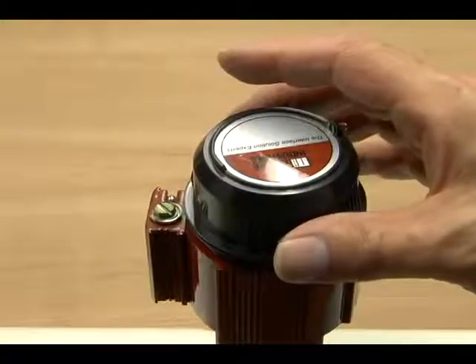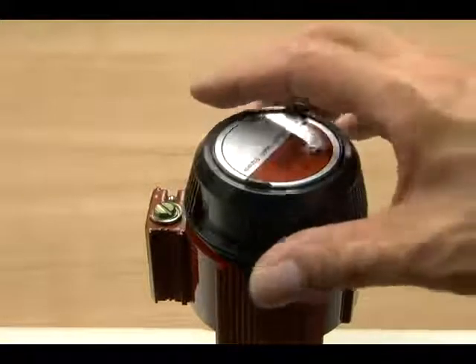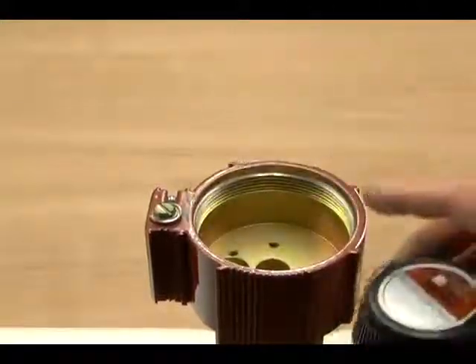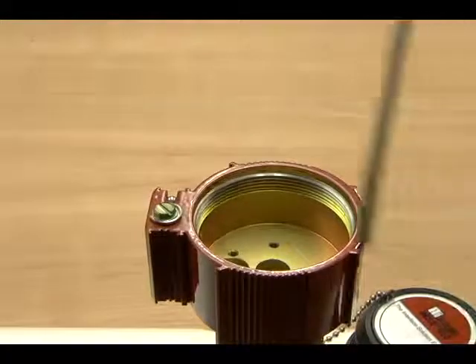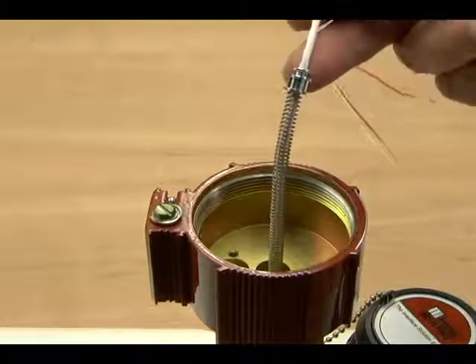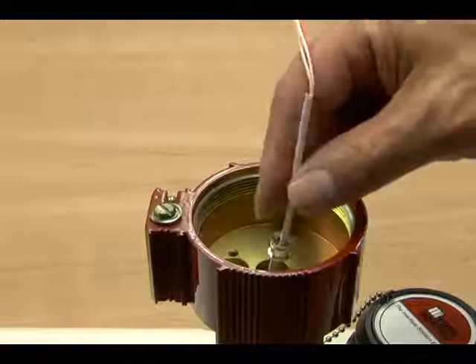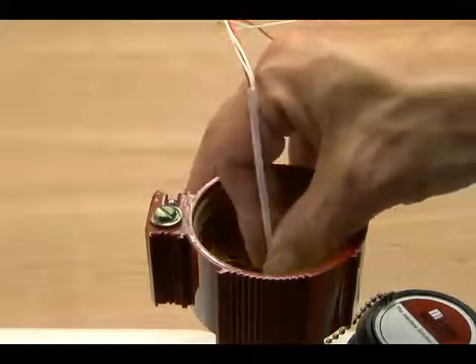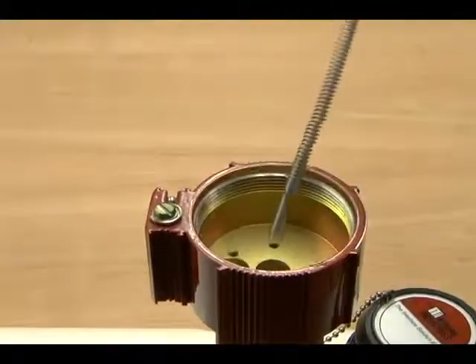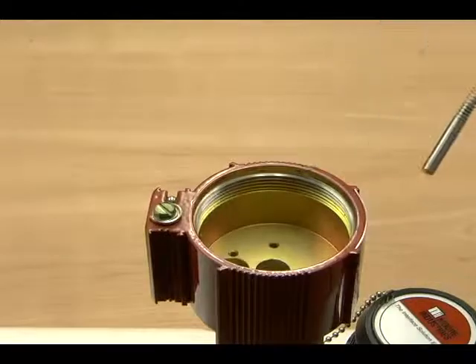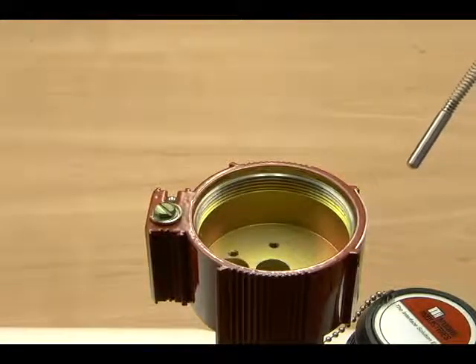If you have head mount enclosures, such as Moore's LH type enclosure, use the same procedure and cut the worm spring so it is an inch or inch and a half longer than the thermal well assembly. Place the ferrule cap over the end of the spring and replace the instrument transmitter in the enclosure. The transmitter will put pressure on the spring and hold it in place.